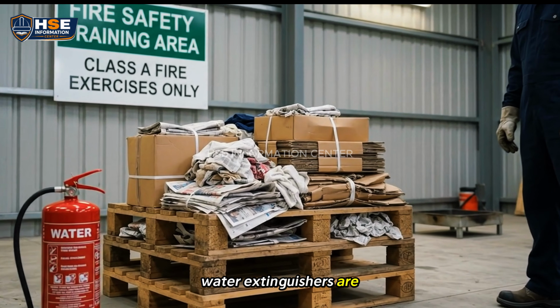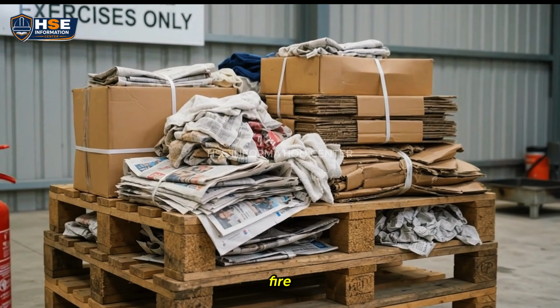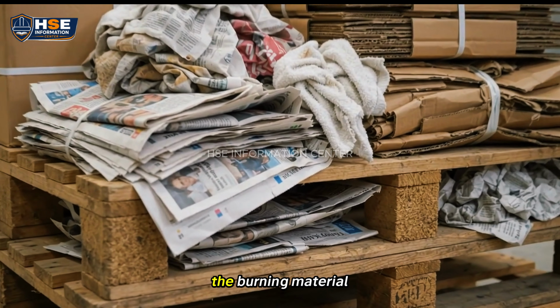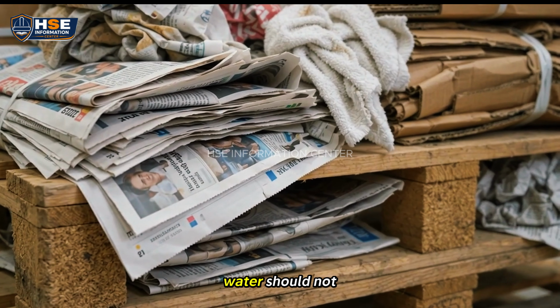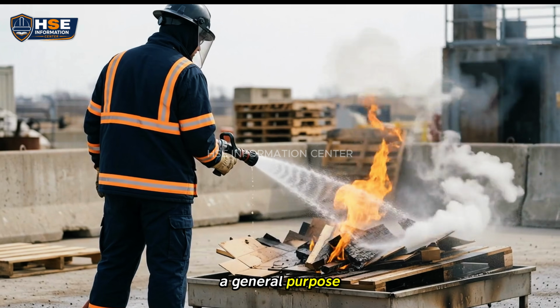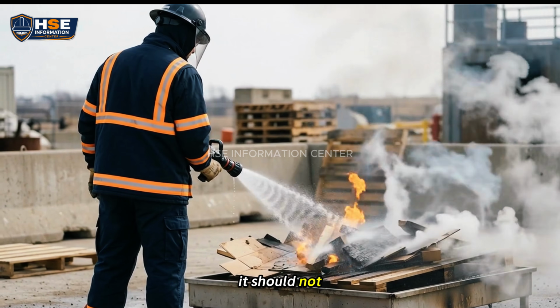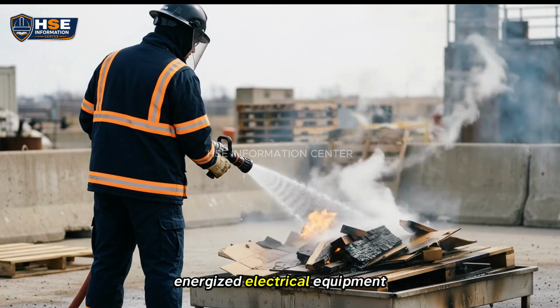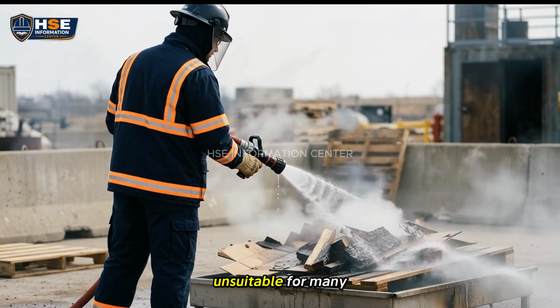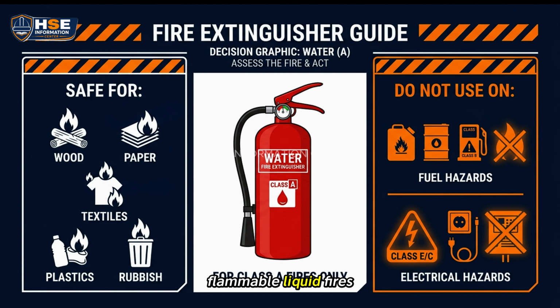Water extinguishers are commonly used for this type of fire because water cools the burning material. Water should not be treated as a general-purpose solution. It should not be used on energized electrical equipment. It is also unsuitable for many flammable liquid fires. Using the wrong agent can spread the hazard or expose the user to additional danger.